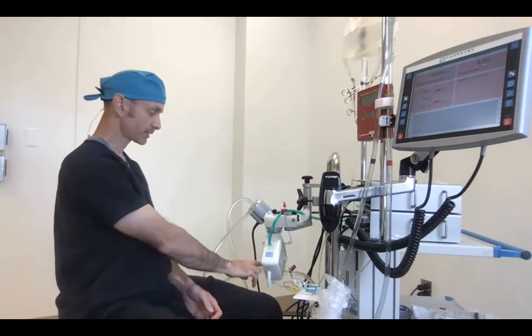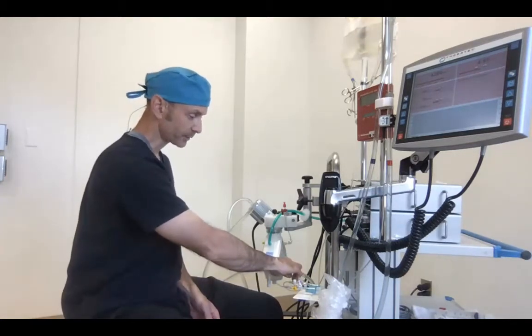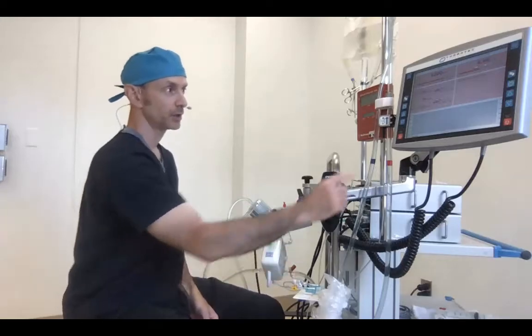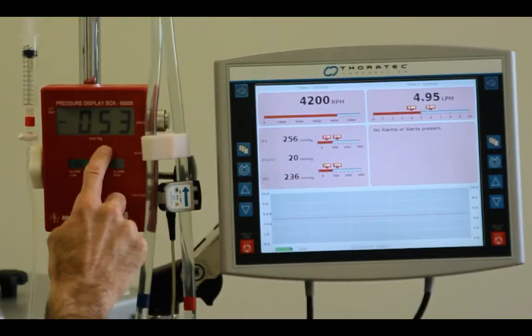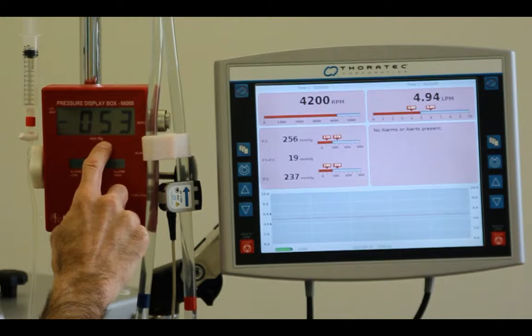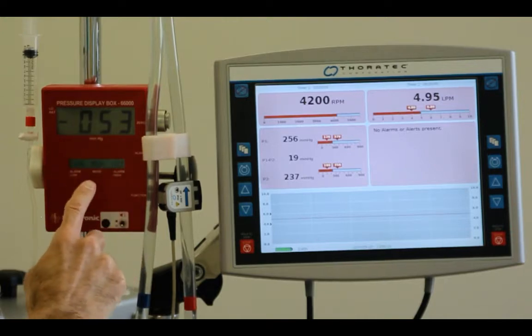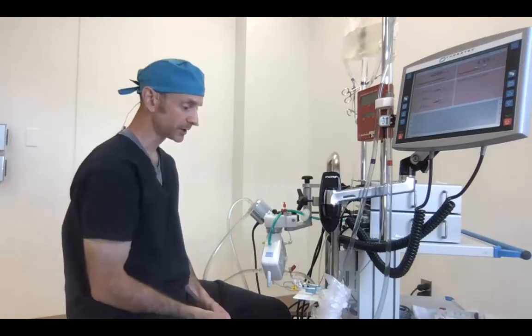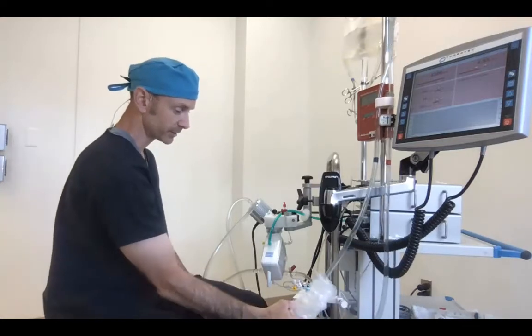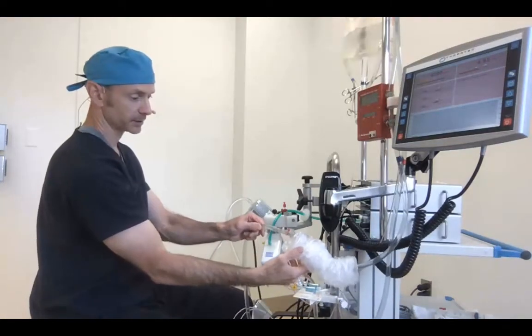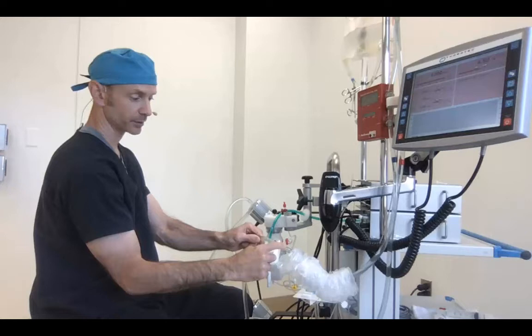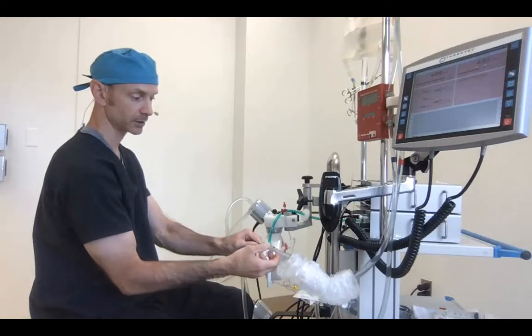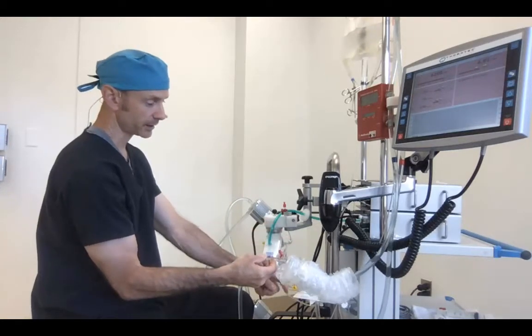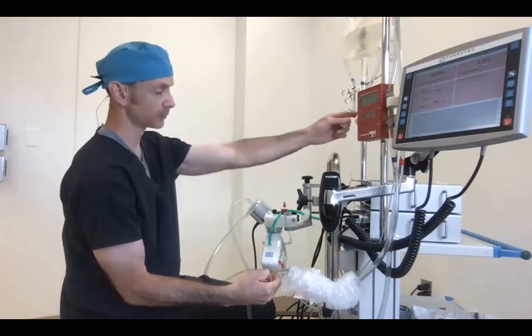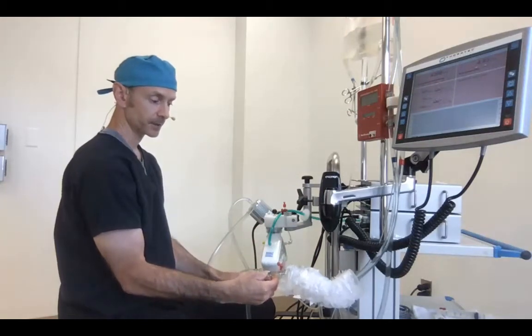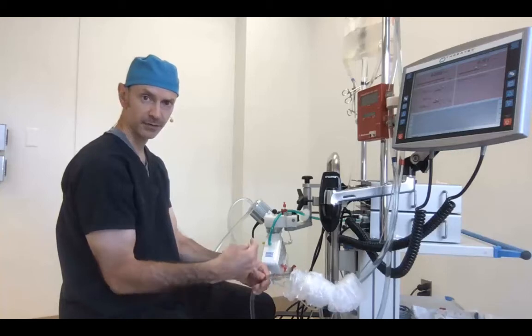Now, in addition to monitoring pre-membrane pressure and post-membrane pressure on P1 and P2 of our Centrimag system, we also have the venous line pressure tapped in. I put this in here just for this demonstration. Clinically, we wouldn't normally cut the venous line like we've done here. Here I cut the venous line and put in a 3/8 straight luer with a luer lock, and I connected that up to our red box disposable set. There's a risk associated with this. We'll try and demonstrate it at the end of the video.